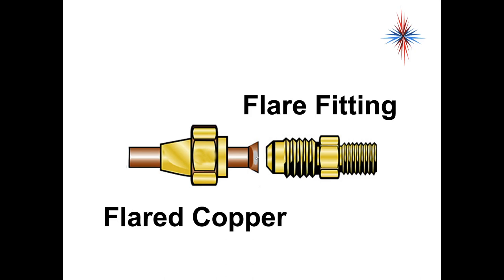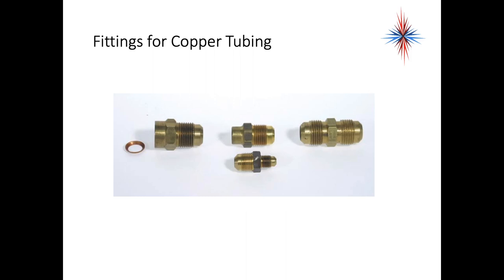Several different fittings are shown here for copper tubing. If you ever see a fitting with that small copper ring there, that's a compression fitting. We do not want to use those in air conditioning and refrigeration as well as oil. Don't use compression fittings. You only want to use flare fittings of some sort. There's reducers, there's other fittings, but don't use the compression fittings if you can at all avoid it.